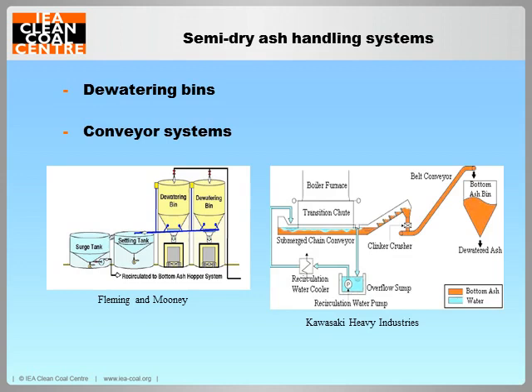Right, in semi-dry ash handling systems, the ash is dewatered after it's been cooled with water. Recycling this water could result in zero liquid discharge from the ash handling system, as well as saving water. Commercial systems are available, and you can dewater the wet ash either in a batch type system using dewatering bins or on a continuous removal conveyor system.